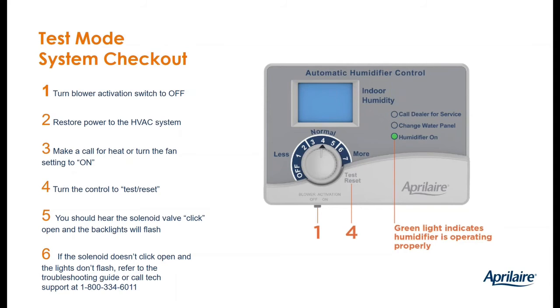Remember, test mode's only good for a minute. So if you turn it to test mode and then walk over to the thermostat and make a heat call, by the time you get back to the humidistat, your minute's already expired. So heat call first, test mode second. When you turn it to test mode, you'll hear a click at the humidistat. You shouldn't see any error codes, and you should hear a click as the solenoid valve opens up on the humidifier. If that happens, the wiring's good. Then just check to make sure you've got water going through the humidifier, then you know your plumbing's good, and you know that you're going to be good once you get into the heating season. So turn the dial from test mode back to whatever number you want to set it to.